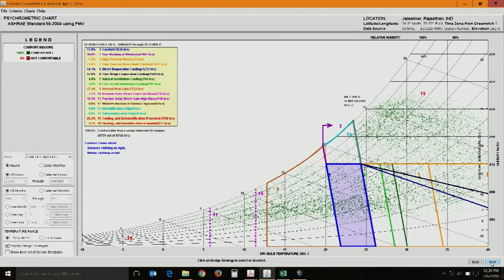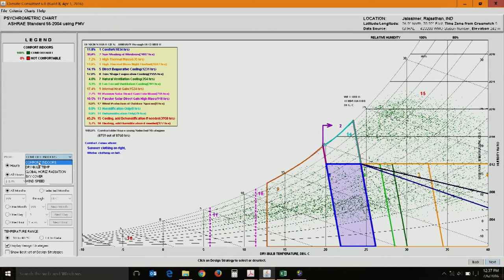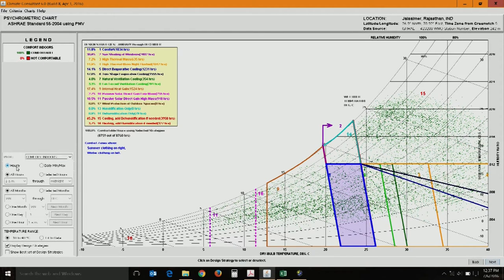The previous features are of general interest for design projects, but the psychrometric/bioclimatic chart is the interesting part for making design decisions for specific climatic conditions. The chart shows what percentage of hours are comfortable indoors and allows you to choose what to plot — comfort indoor, dry bulb temperature, etc. Plotting hourly values gives you a dot for each of the 8,760 hours in the year, representing temperature versus humidity at each hour.